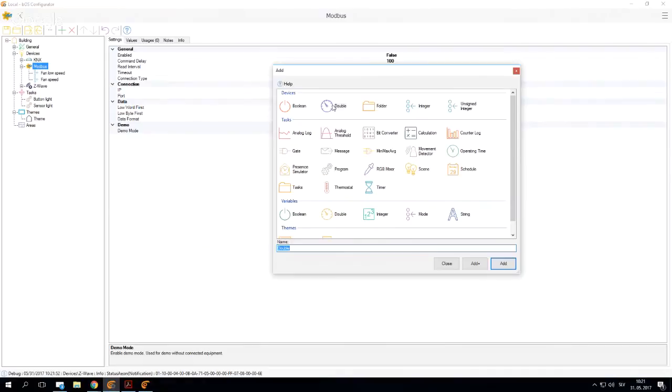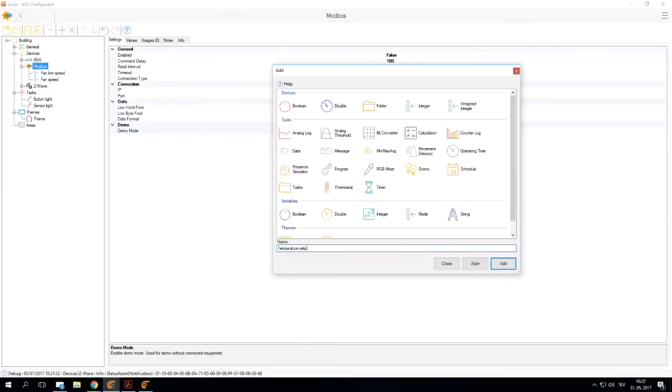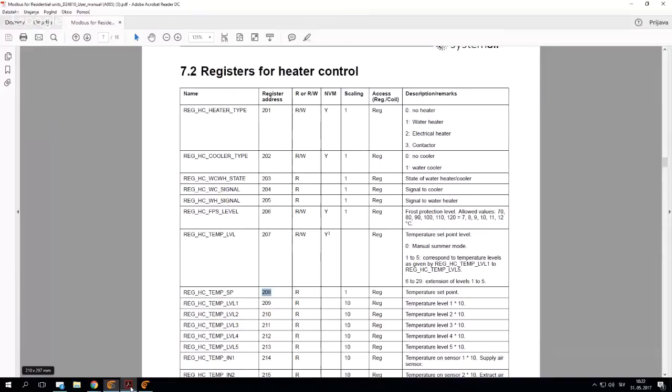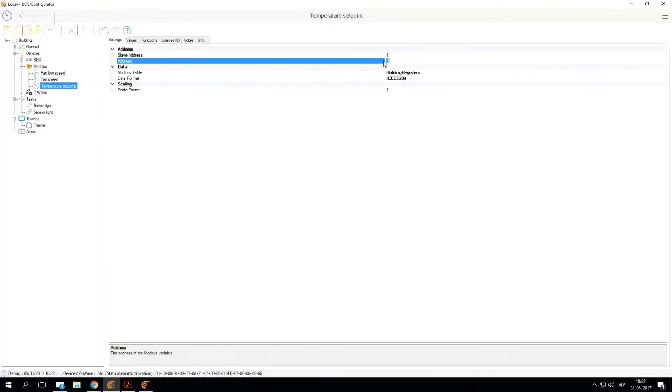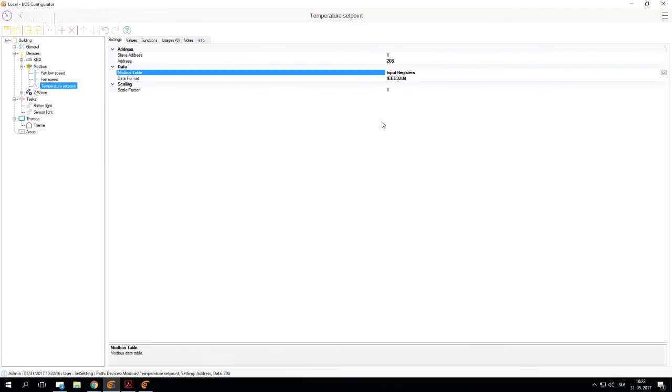So we're going to use our double here. I'm going to name it temperature set point. We go through the whole procedure. Let's say the address is 208 and it's only read, so we can change this to input. And we can change this data table to signed 16 bit.